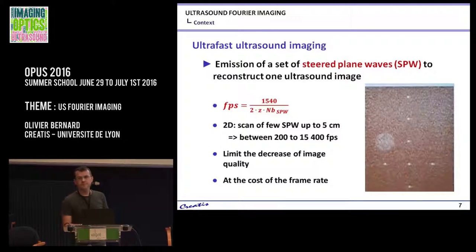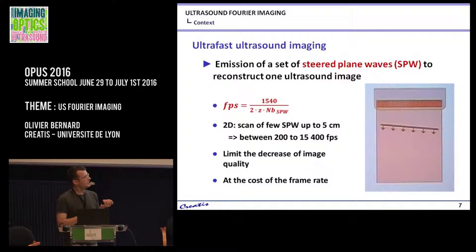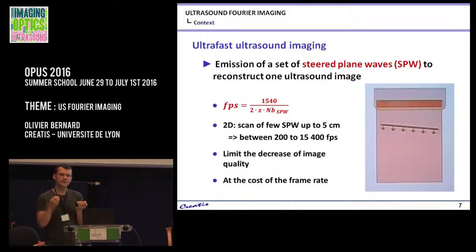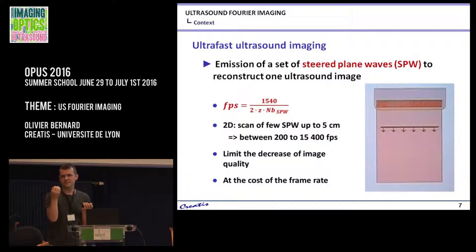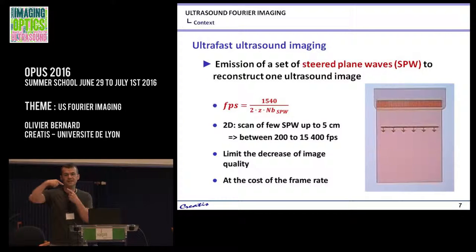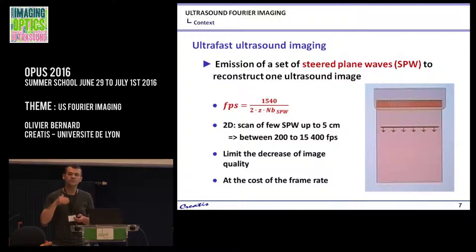Why does the plane wave have to be steered? Imagine you have only one point scatterer. If you reconstruct the image, you will have a typical artifact. With a steered plane wave, this artifact will not be exactly the same. By doing the summation, you suppress those artifacts and increase the signal information. This is the reason why you really need to do the steering.